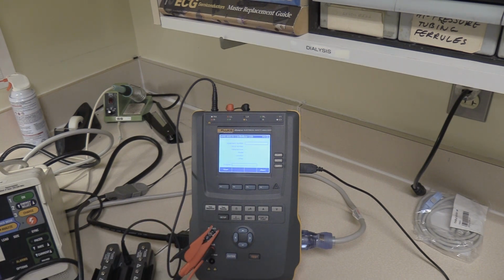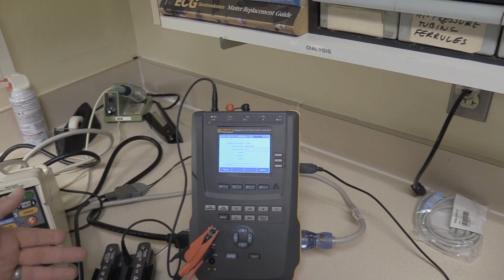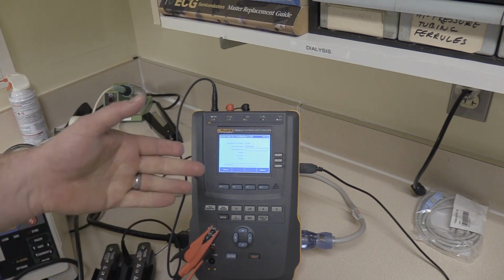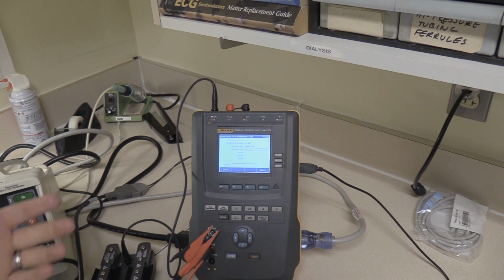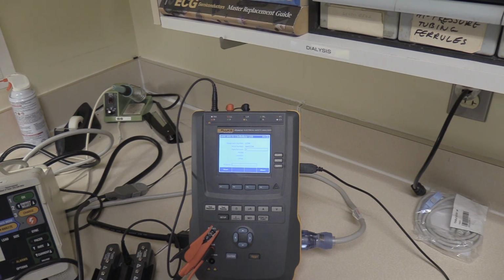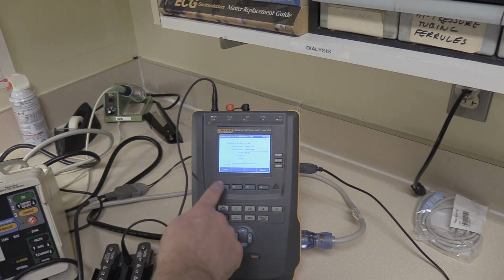And we're going to type in the equipment's identifier tag. And just for today, we're going to call it defibrillator 1234. And we're going to record a serial number in, and we're going to call it test 1234. That's how we're going to pull back the name in the future. We're going to skip the manufacturer because this one's already in our system. Or it's just as easy to type it in. And we'll type in the model number as LifePak20. And we're going to go ahead and start the test by pushing F1.